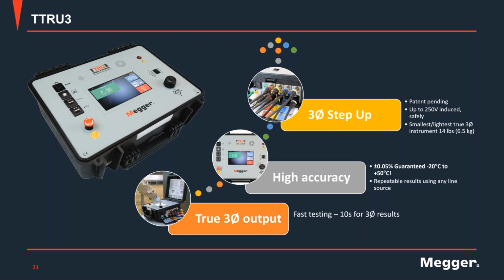The first one, and hence the name, is a true three-phase output. So the unit will be able to energize the three phases of my transformer simultaneously. Again, hence the name. Higher accuracy, plus and minus 0.05%. And really important, this very high accuracy is guaranteed in a very wide range of temperatures, from minus 20 degrees Celsius all the way to 50 degrees Celsius. That means repeatable results no matter the conditions.